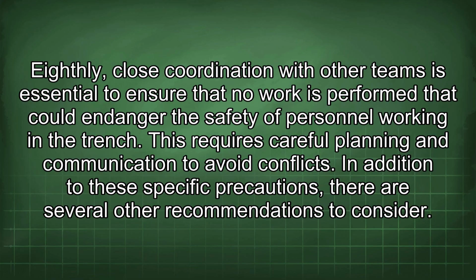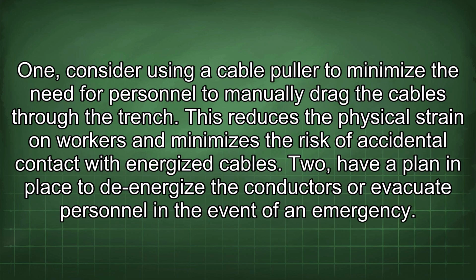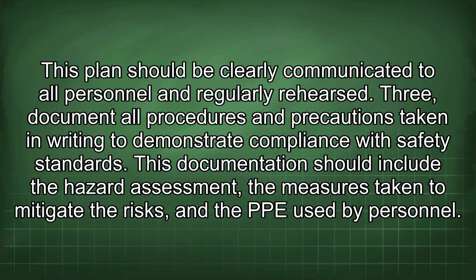In addition to these specific precautions, there are several other recommendations to consider. 1. Consider using a cable puller to minimize the need for personnel to manually drag the cables through the trench. This reduces the physical strain on workers and minimizes the risk of accidental contact with energized cables. 2. Have a plan in place to de-energize the conductors or evacuate personnel in the event of an emergency. This plan should be clearly communicated to all personnel and regularly rehearsed. 3. Document all procedures and precautions taken in writing to demonstrate compliance with safety standards. This documentation should include the hazard assessment, the measures taken to mitigate the risks, and the PPE used by personnel.